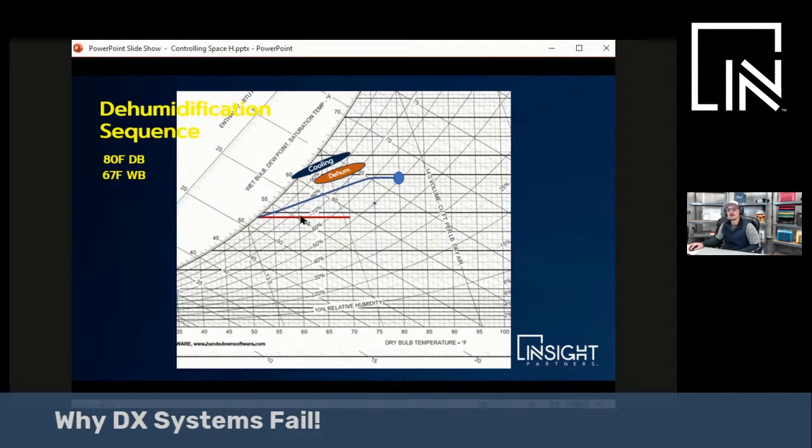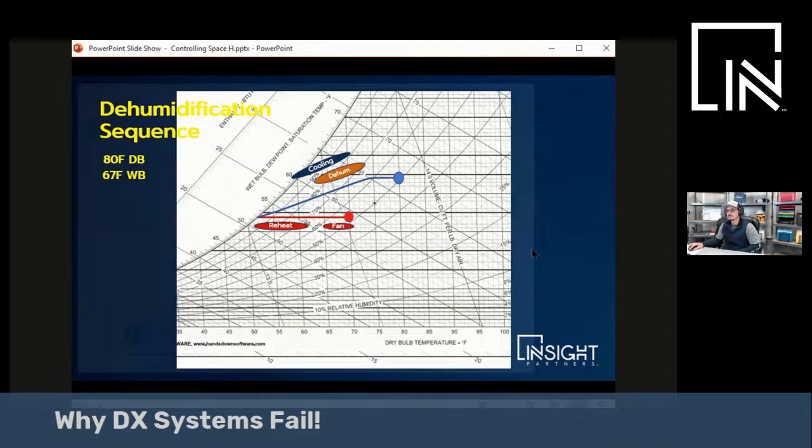We would heat the air back up along this line here using the reheat. And then we get a couple degrees from the fan heat arriving at our predetermined leaving air temperature, which is determined basically by the unit control.